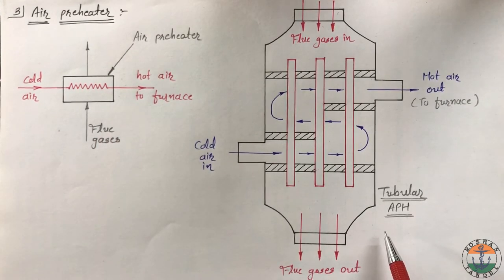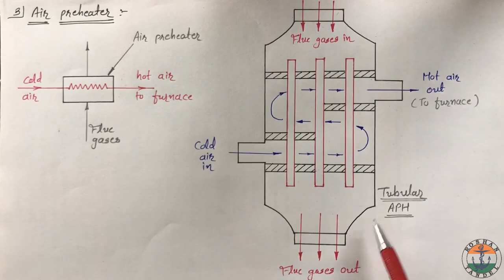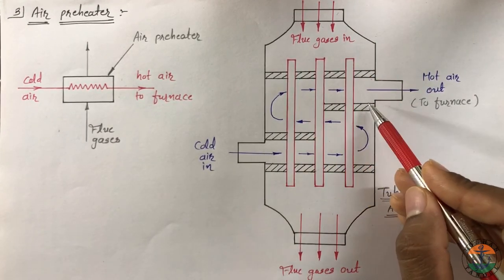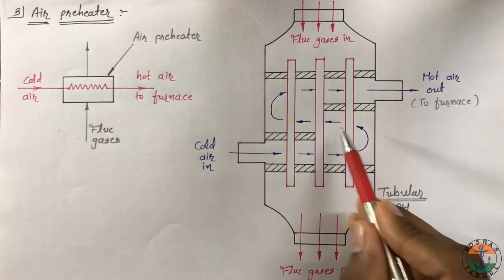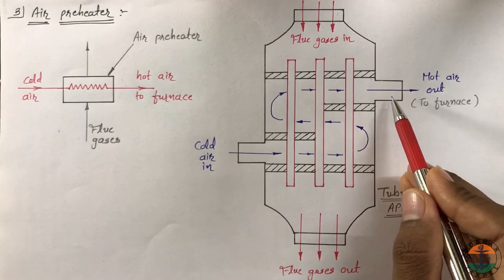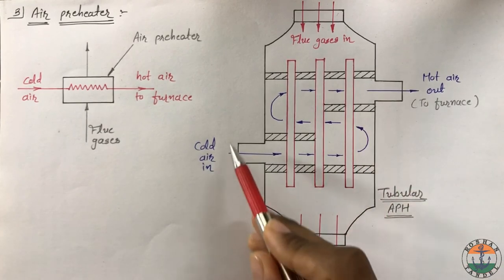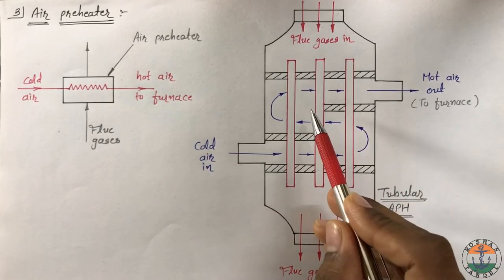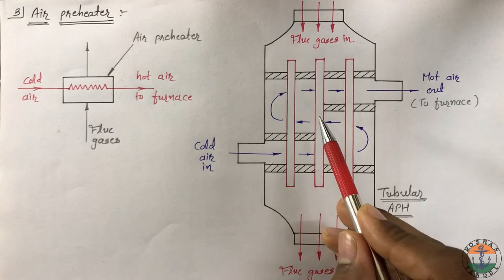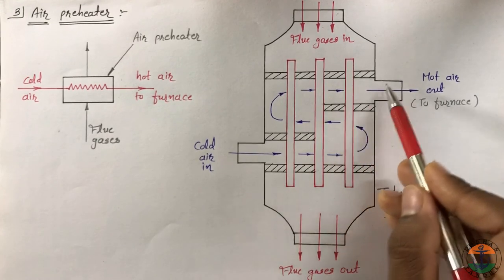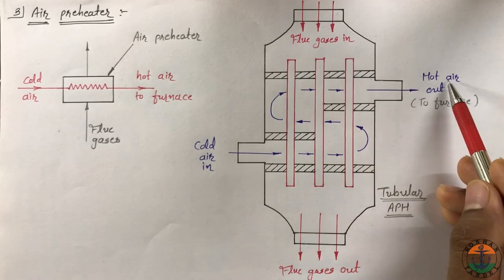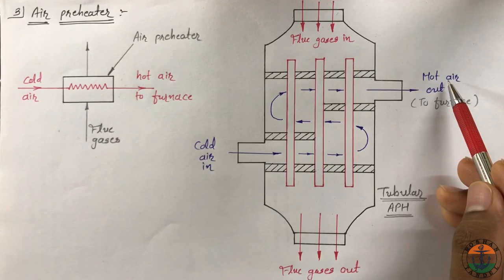Tubular air preheater is shown here, in which flue gases flow through these tubes and air flows in zigzag manner around them. Cold air is supplied and some amount of heat from exhaust gases is recovered. Heated air is then supplied to the furnace for combustion of fuel.